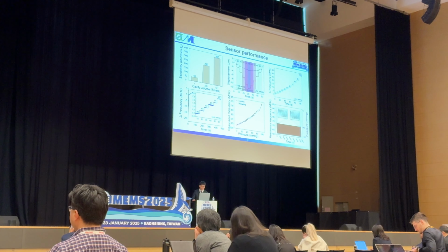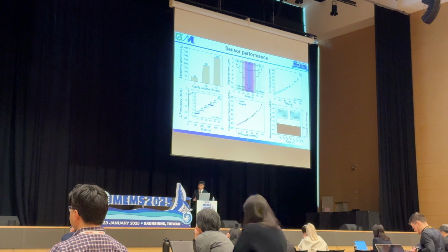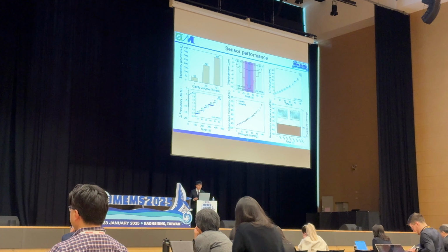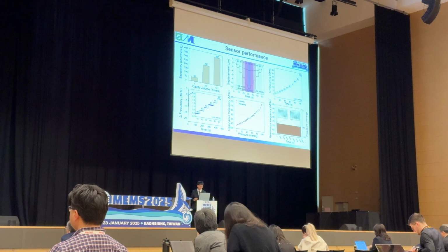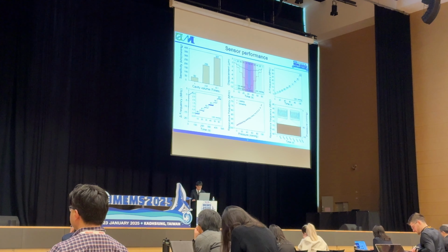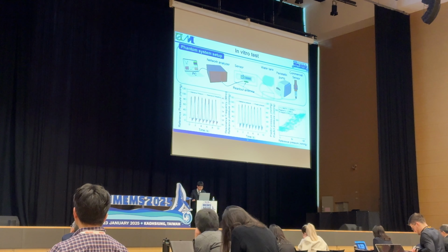And then we further test the sensor's diaphragm displacement by laser micrometer to confirm that our ultra-sensitivity sensor has a diaphragm with larger displacement. Then we also test the sensor's resolution and also the long-term stability. So next step, we move our sensors into the phantom system.